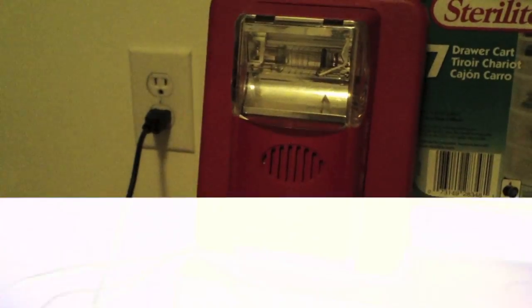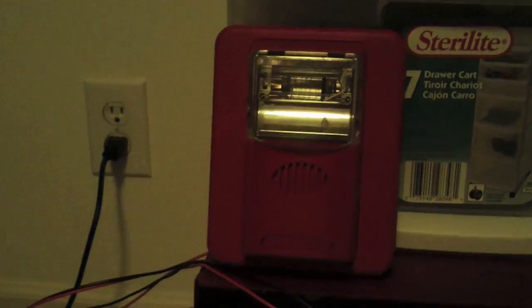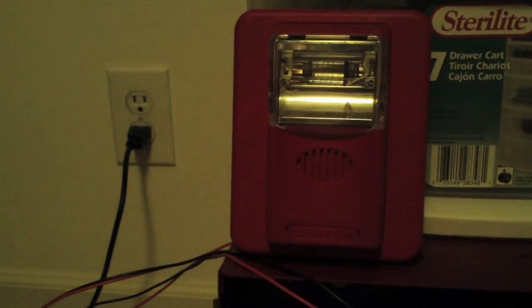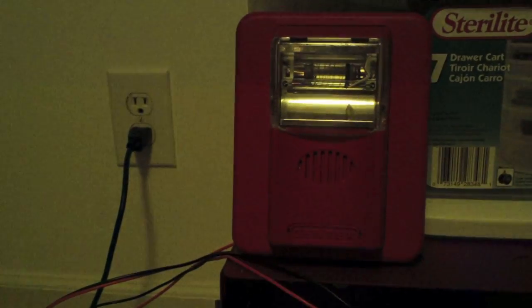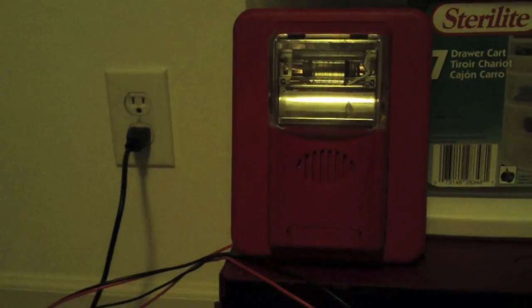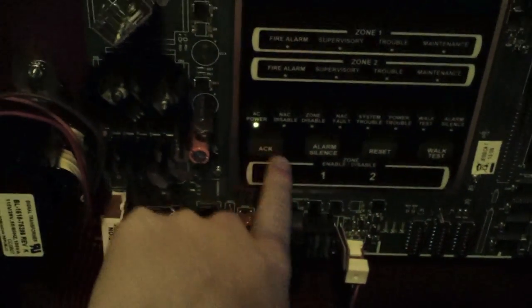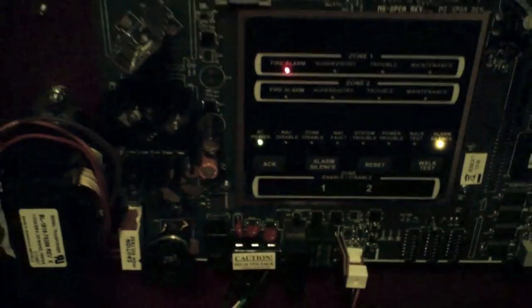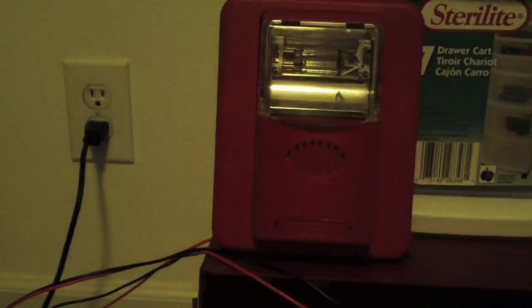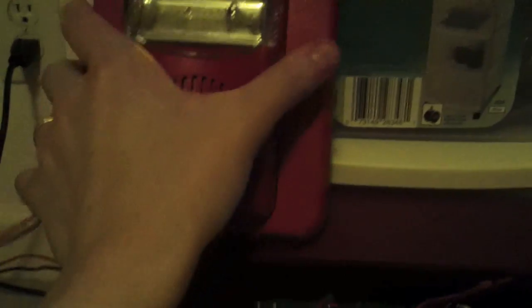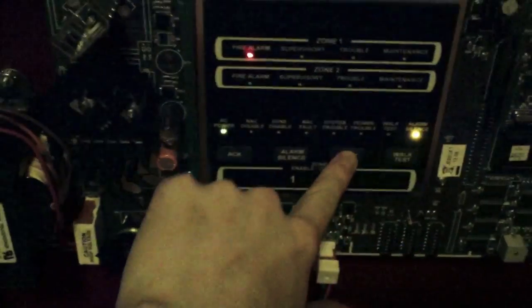So let's go ahead and test it out. Gentex Sync, here we come. And we have audible silence with the synchronization, and it's only being run on two wires, as you can see. Let's make sure that stays up there. Perfect. And let's go ahead and just reset the system.